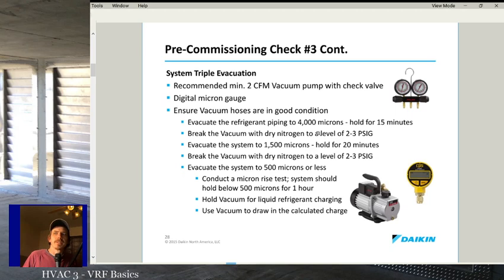Then evacuate the system again down to about 1,500-ish microns. Hold for a few minutes, make sure you're good, break it with nitrogen again, and purge it around. Then evacuate the system to 500 microns or less. If you can get down to 500 microns, you're pretty good on leaks. You may not be perfect, but you're pretty good. And you've got a pretty dry system.